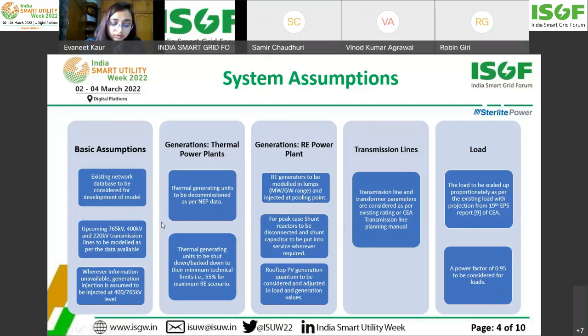For upcoming RE generations, these are modeled in lumps of megawatt or gigawatt range and injected at pooling points. For peak case scenarios, shunt reactors are disconnected and shunt capacitors put into service wherever required. In this scenario, rooftop PV generation is also considered, and this quantum is adjusted in the load and generation values.